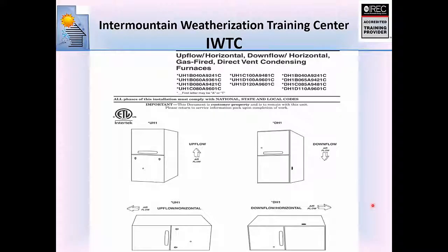Okay, here's just a quick thing. This is a manufacturer's installation guide, and it just shows different configurations of furnaces. So this particular manufacturer, their upflow furnace, again, the air blower's in the bottom, air blows up. They use a U as the designator in their model number for upflow. Their upflow furnace can be placed in a horizontal left condition. So I can take this furnace, lay it on its left side. We call this horizontal left.